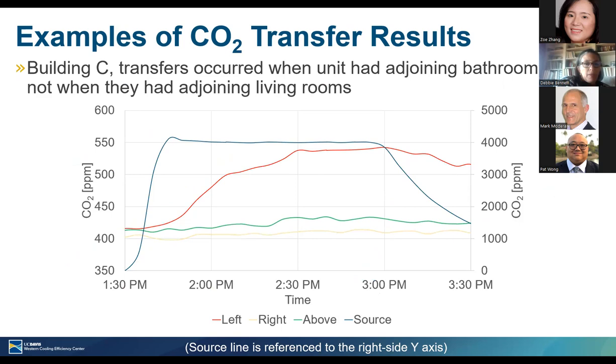In building C, there was one wall with bathrooms and one wall with living rooms. Depending on whether you were crossing a bathroom wall or a living room wall, we saw differences. Crossing over a living room wall, the CO2 level didn't budge. Whereas crossing over a bathroom wall, we did see the CO2 level increasing in the receiving unit.